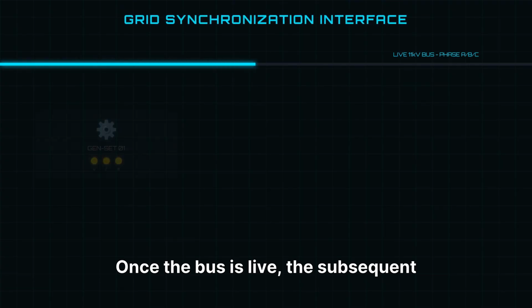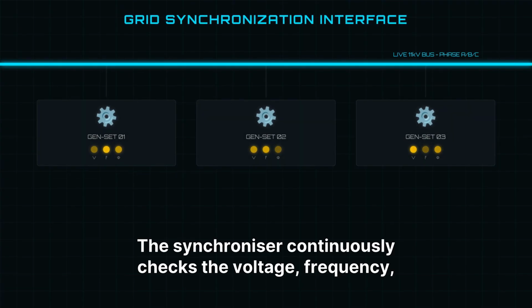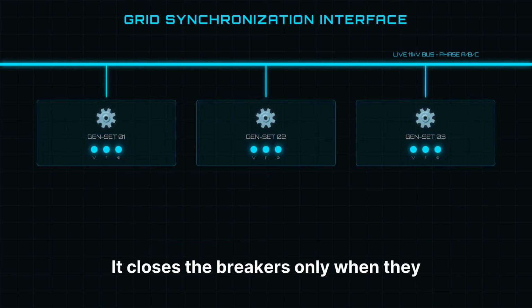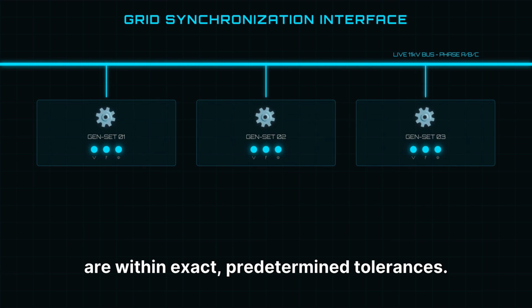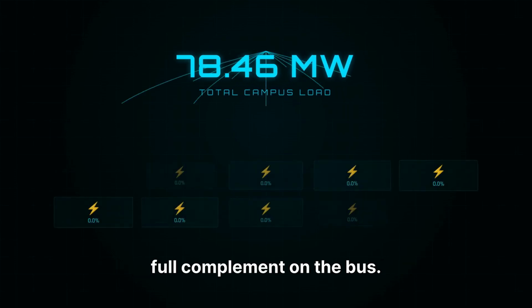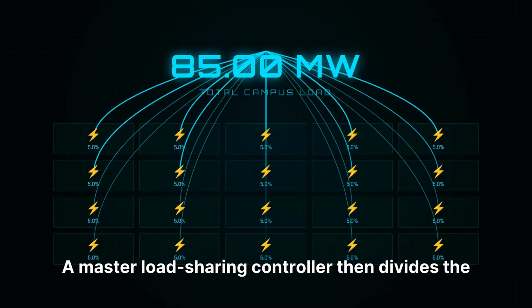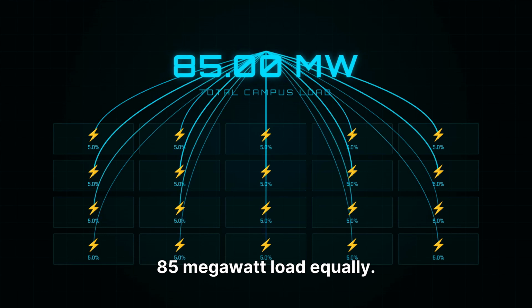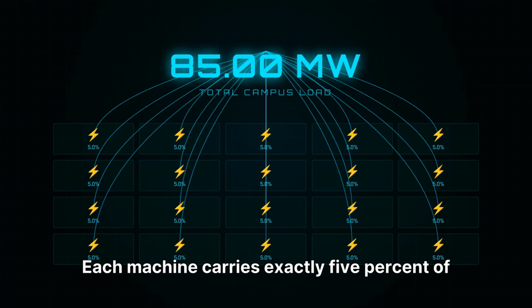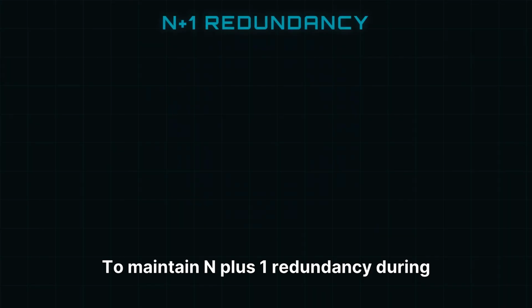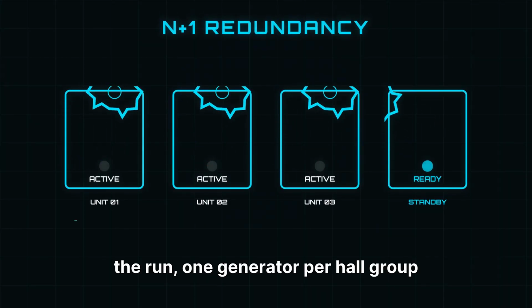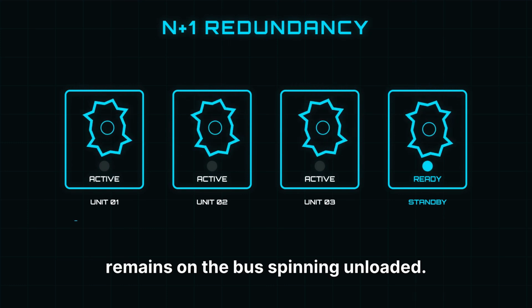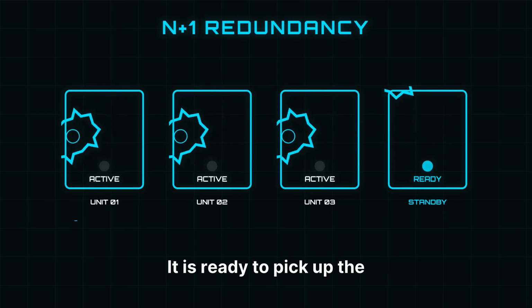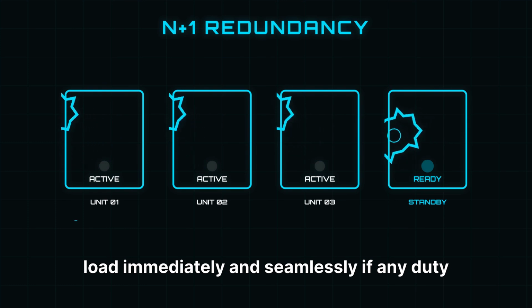Once the bus is live, the subsequent machines begin to parallel. The synchronizer continuously checks the voltage, frequency, and phase angle. It closes the breakers only when they are within exact, predetermined tolerances. By approximately 25 seconds, we have a full complement on the bus. A master load sharing controller then divides the 85 megawatt load equally. Each machine carries exactly 5% of the total demand. To maintain N+1 redundancy during the run, 1 generator per hall group remains on the bus spinning unloaded. It is ready to pick up the load immediately and seamlessly if any duty unit trips.